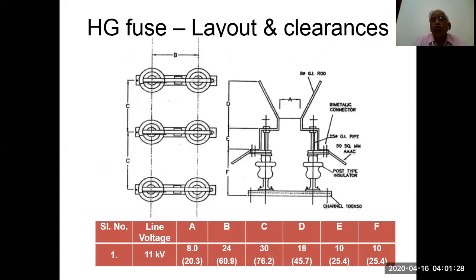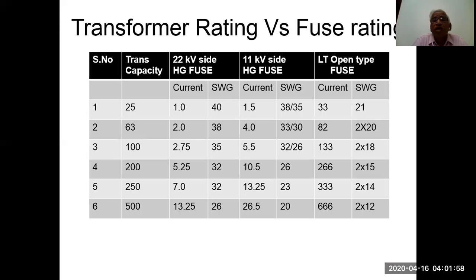HG fuse layout and clearances are very important. When you are putting in the HG fuse, there is a distance between the fuses, as you can see in table A. That gap has to be maintained. The bend given is very important. The bend is to the outside, and it should appear like a horn gap. The dimensions D, E, F and A as mentioned in the diagram have to be measured for the particular voltage level. Now, transformer rating and fuse rating.